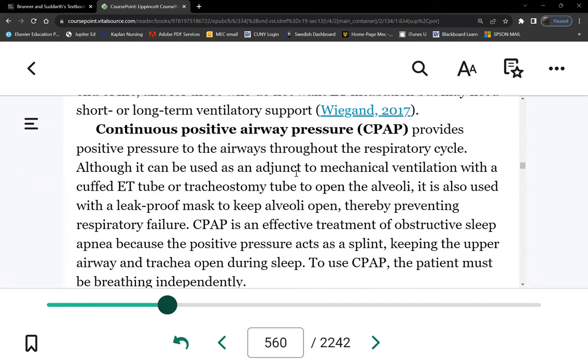Let's differentiate between CPAP and BiPAP. CPAP stands for continuous positive airway pressure. Since it's continuous, the pressure exerted by the machine does not change — it blows air. But this device is not a ventilator. A ventilator is sophisticated equipment; you can program a ventilator far more than a CPAP. CPAP simply lets you set the numbers — how much pressure you want — and it does that. Even if the patient dies, it will continue to blow air with no warning.